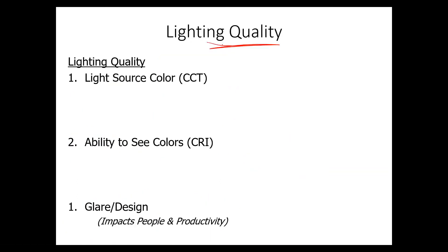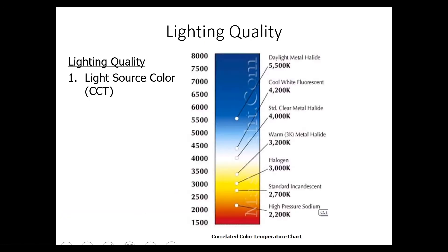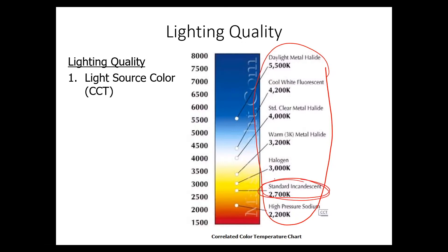Now let's talk about lighting quality, which is composed of three primary areas: light source color, color rendering index, and the relationship between glare and design. The color of the light source is the color you see when you look at the light bulb. Different types of lamps have different color temperatures. Standard incandescent would have a color temperature of around 2700 Kelvin — meaning if this were a star or some hot object, it would be emanating wavelengths of light representative of a 2700 Kelvin surface temperature.